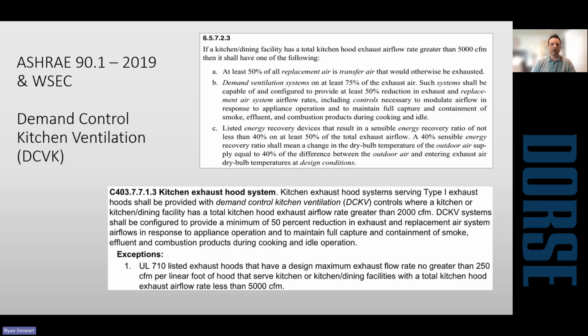So ASHRAE 90.1 and Washington State Energy Code require demand control ventilation if the exhaust airflow is greater than 2,000 CFM. And they say that it needs to be configured to provide a minimum of a 50% reduction in exhaust and supply air in response to the appliance operation, while maintaining full capture and containment of smoke and grease-laden vapors. They do offer an exception. Hoods that are less than 5,000 total CFM and less than 250 per foot for airflow are exempt.